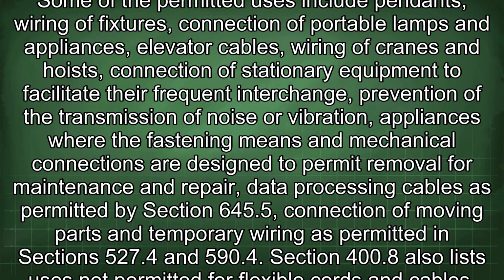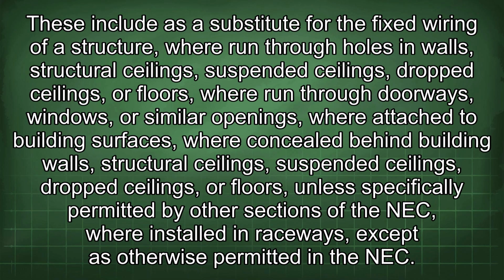Section 400.8 also lists uses not permitted for flexible cords and cables. These include as a substitute for the fixed wiring of a structure, where run through holes in walls, structural ceilings, suspended ceilings, drop ceilings, or floors, where run through doorways, windows, or similar openings, where attached to building surfaces, where concealed behind building walls, structural ceilings, suspended ceilings, drop ceilings, or floors, unless specifically permitted by other sections of the NEC, and where installed in raceways, except as otherwise permitted in the NEC.